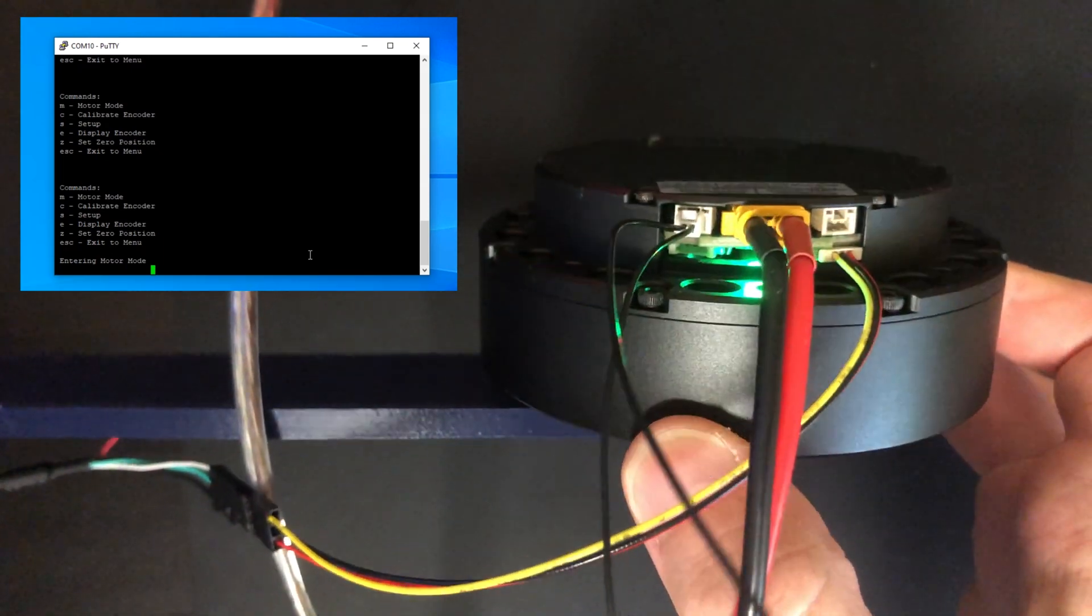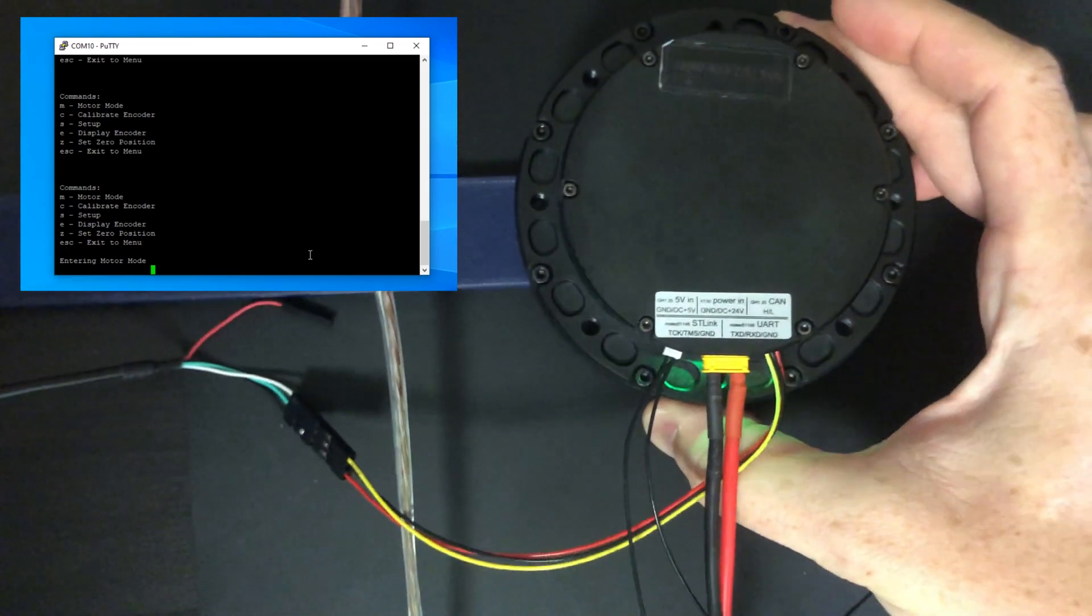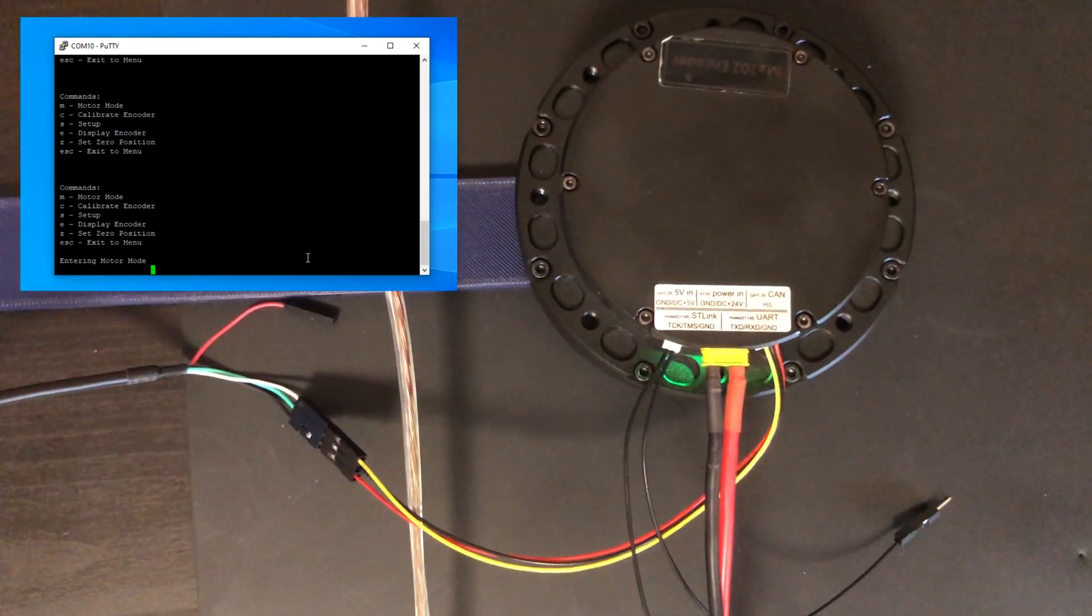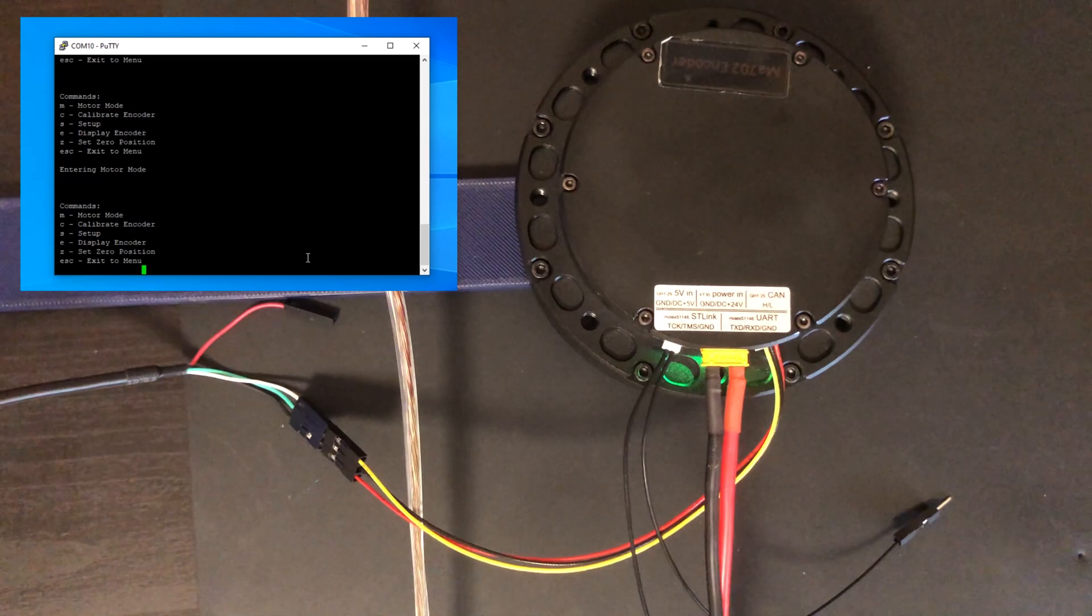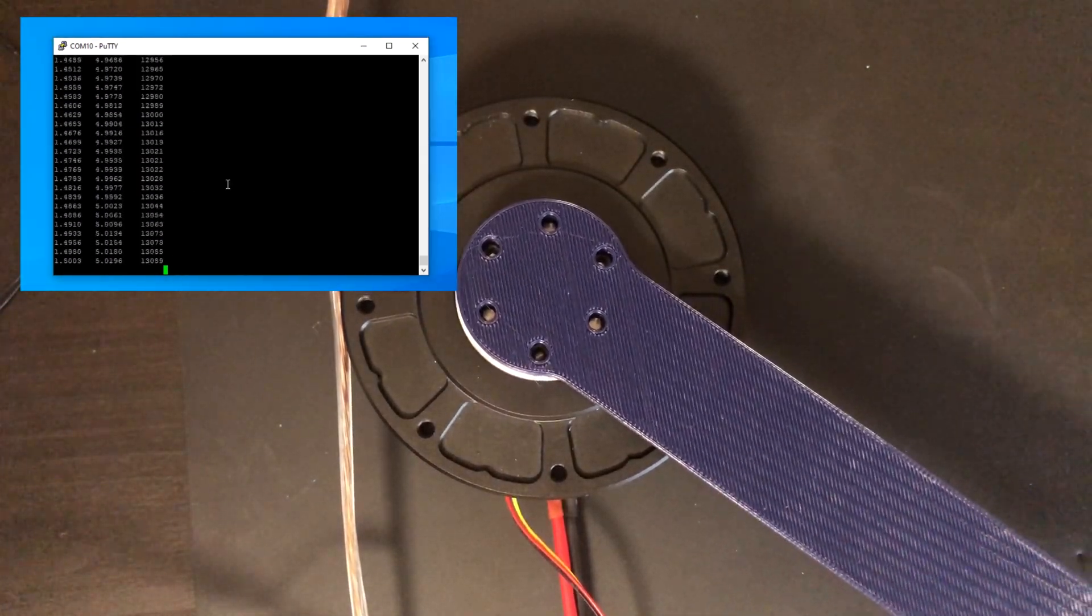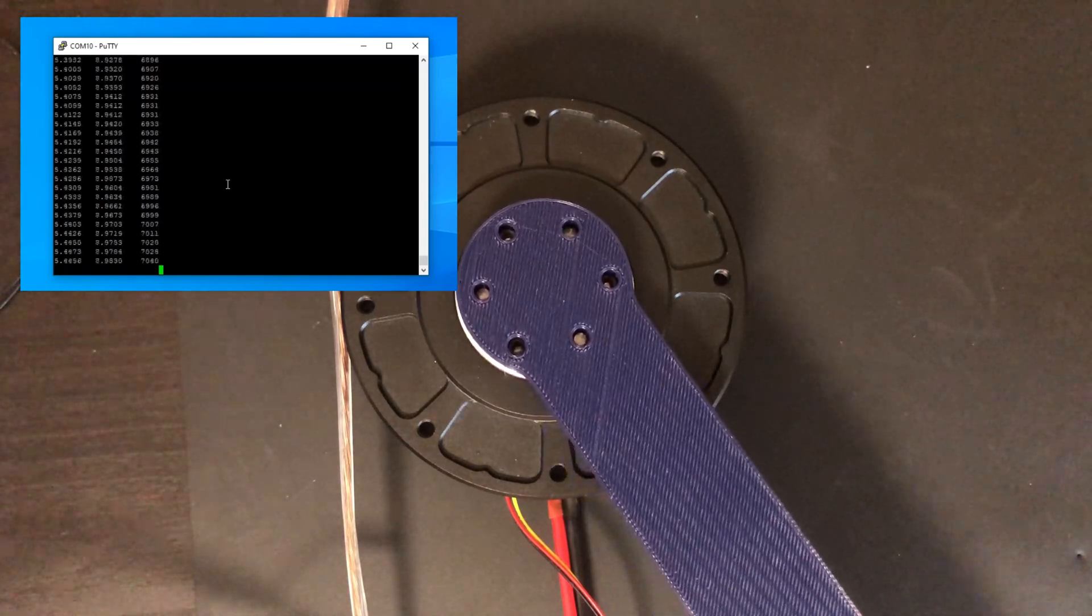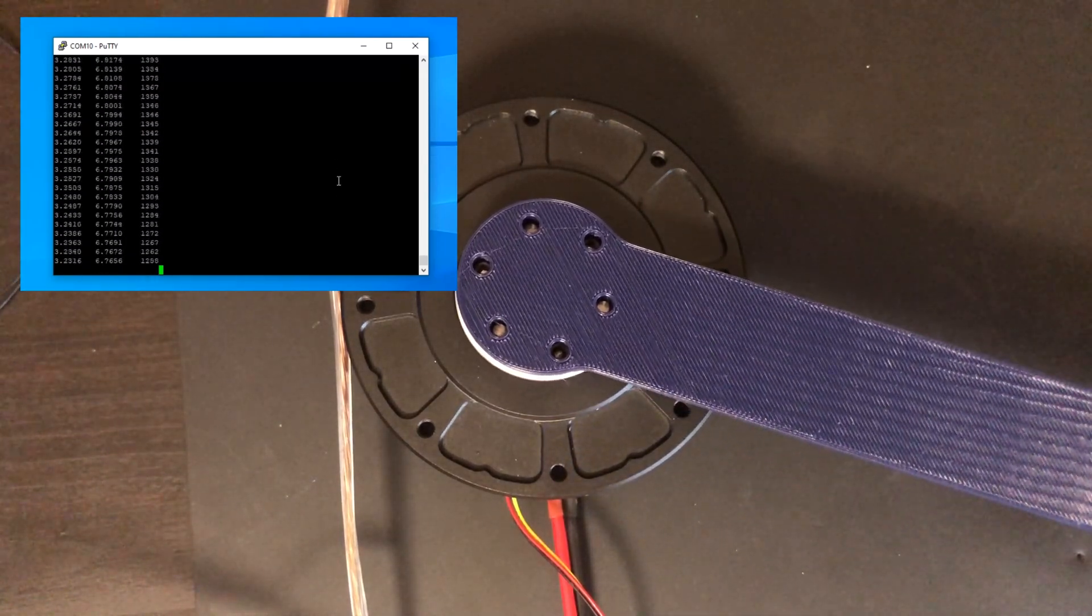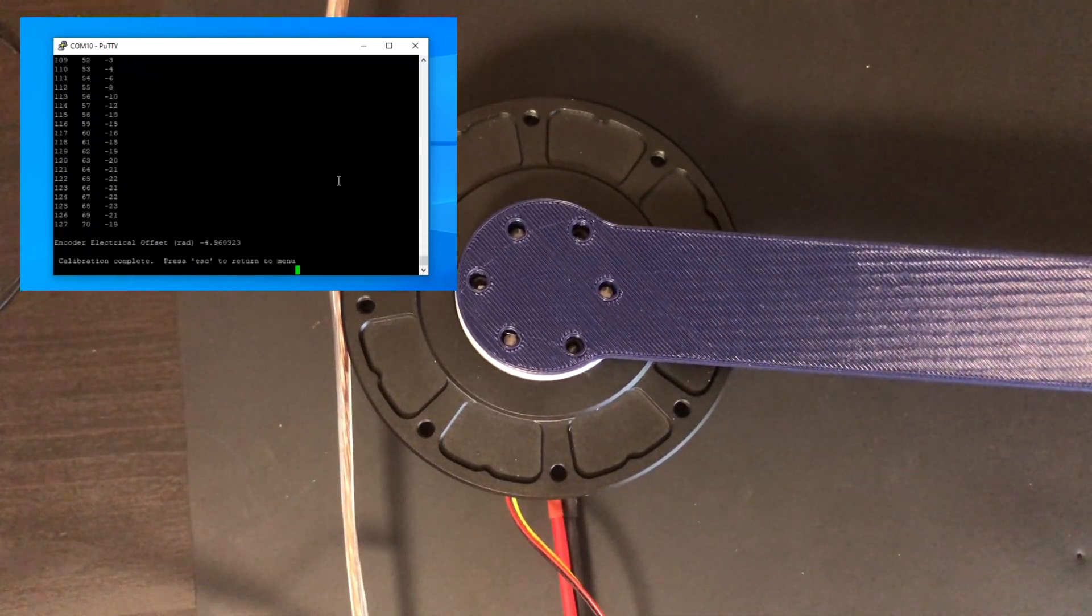Another thing we'll want to do is calibrate the encoder. You should always calibrate the encoder before you use one of these drives. The calibration procedure will automatically execute as soon as you press C. It only takes a few seconds to run and is super important for smooth operation.